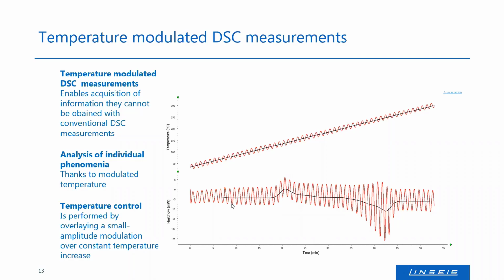At the bottom, you can see an example here. In this case, it's PET with the glass transition, the recrystallization and the melting in a raw curve. So for a conventional measurement, and the red curve here is the temperature modulated way. This looks a bit curious, but we will get some information through this. What we also can already see here is that after the glass point, for example, the amplitudes of our results are higher. And also in the melt, the amplitude gets really high.